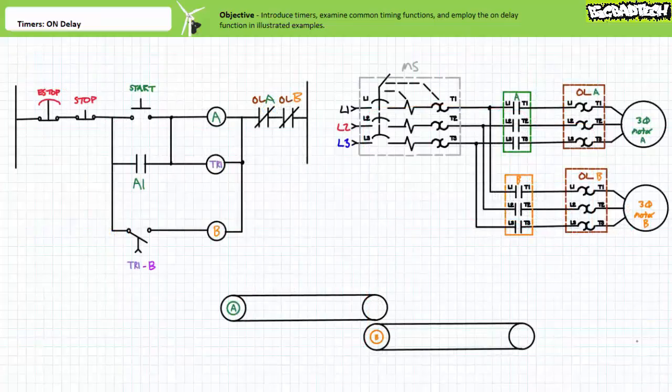Moving on, timers are not exclusively used in electrically controlled hydraulic systems, but can also be used to coordinate the activity of electric motors. Consider a simple motor-driven conveyor belt system with 2 sections, A and B. At the start of the day, both belts are empty, and then a production line starts dropping boxes onto the far end of belt A. Given boxes only get on the belt at the very far end of A, and belt B is empty, it'd be kind of wasteful to spin section B until something was placed on it. Given it would take a predictable amount of time for a box placed at one end of A to reach the other, conveyor belt B could delay starting a time period after belt A has been energized.